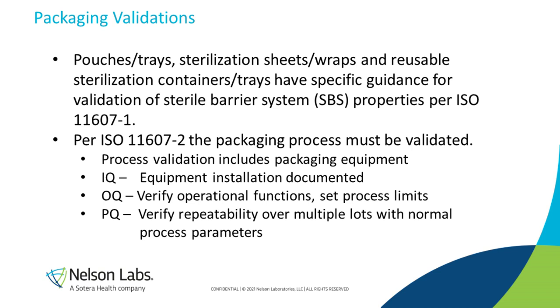Anything that needs to be sterile requires a package or a barrier to protect what's inside from contamination and to maintain the sterility. Sterile barrier packaging is governed by ISO 11607. This document has two parts. Part one is for validating packaging as a sterile barrier — you would test for strength, integrity, and microbial barrier properties in both a new condition and at the end of its expected life. Part two talks about validation of the packaging process, ensuring the packaging equipment produces a consistent, defect-free package day after day.